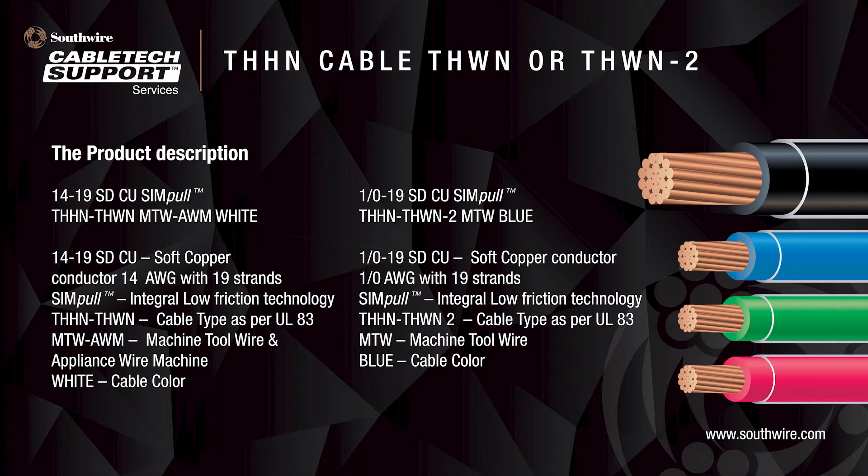The product description can tell us a lot about the cable — for example, the cable size, the type of product, and the color of insulation. In the first example, we have a 14 AWG product with 19 strands. We also see that the product is a Southwire SIMpull branded product that uses integral low friction technology. THHN-THWN are the UL-83 type designations. The product is also rated for MTW and AWM and can be used as machine tool wiring and for wiring in appliances. Lastly, the color is white.